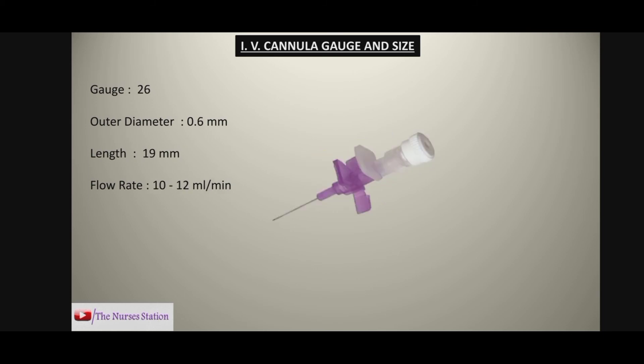Lastly, we have the violet colored cannula with a gauge size of 26, outer diameter of 0.6 mm, and length of 19 mm. The flow rate in this type is 10 to 12 milliliters per minute. The violet and yellow colored cannulas are usually used in the pediatric and neonatal population because they are very small, with a very low flow rate and very small diameter compared to other cannula types.